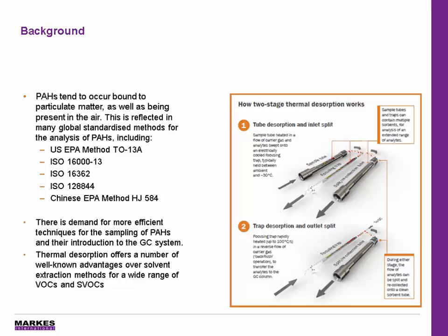To the right of the slide, we can see a diagram showing how thermal desorption works, broken down into two stages. The first stage is where the sample tube, which has had ambient air pumped onto it, is placed inside the thermal desorption instrument. A flow of gas is applied and the compounds of interest are swept from the tube onto a focusing trap. This focusing trap is typically held anywhere between room temperature down to minus 30 degrees, depending on the analytes of interest. At this point we can split — termed the inlet split — and this split can be recollected onto a clean sorbent tube.